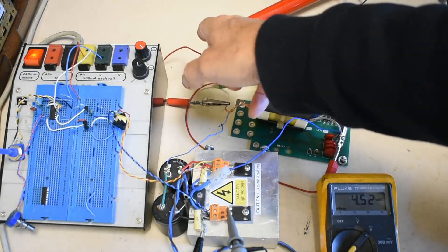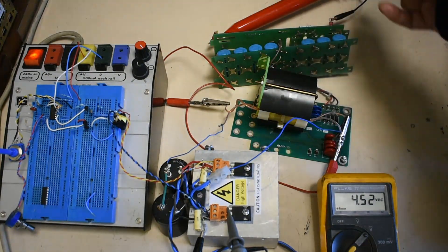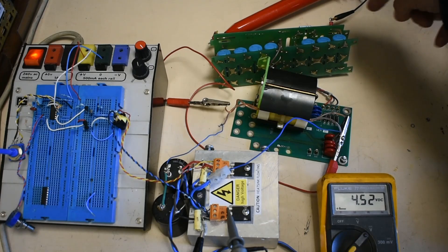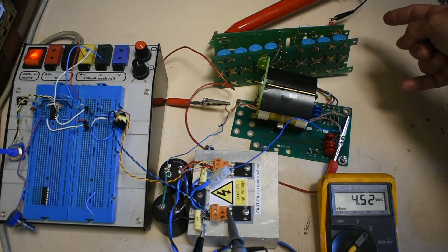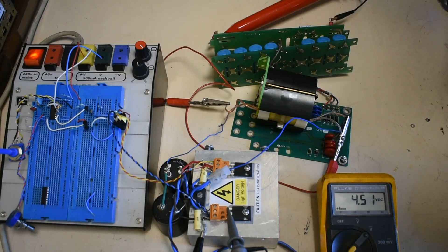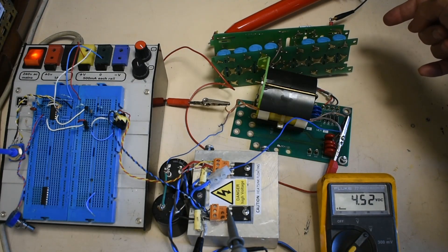Now it's 4.5 kV from one side to the other. So I have to be careful because this side hasn't got the insulation for the center zero point. So this will be 2 kV on this point to ground.